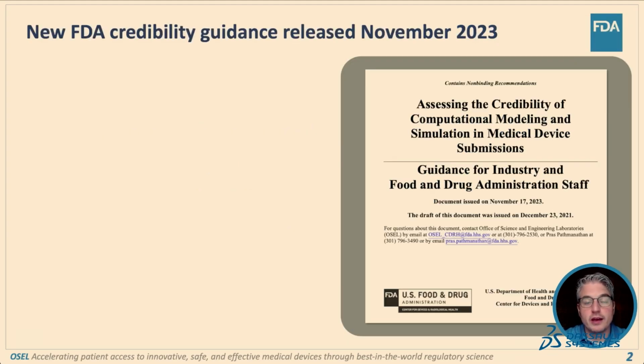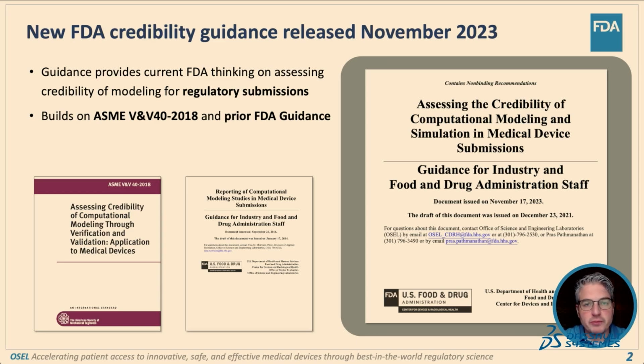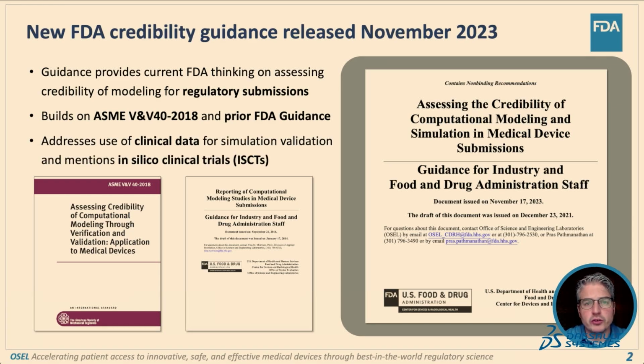First, some context. About a year ago, November 2023, FDA published a final guidance assessing the credibility of computational modeling and simulation in medical device submissions. The guidance provides FDA's current thinking on credibility assessment for modeling studies used to support regulatory submissions. The guidance builds upon ASME V&V 40 2018 and prior FDA guidance for reporting of computational modeling studies. The guidance also provides perspective on new principles, such as the reliance on clinical data to support simulation validation, and the emerging topic of using modeling and simulation to drive in silico clinical trials for medical devices.